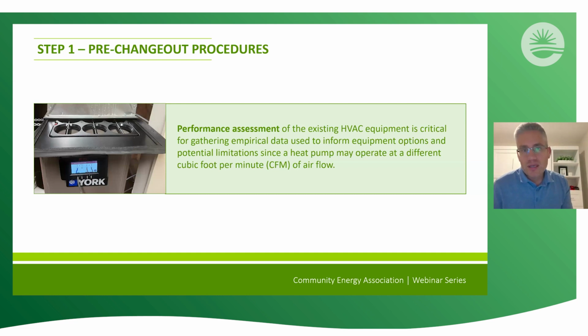And then the last one is the performance assessment. This is a bit more on the technical side, I guess, but contractors, aside from collecting the data to do load calculations, understanding how your existing equipment is performing from the homeowner's point of view, really need to be doing some data collection and performance testing of your existing system to determine any type of limitations or issues with putting in a heat pump within an existing home that has existing ductwork capacity.